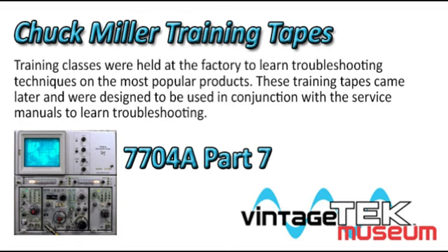R3039 grounds the cover, which covers this inverter circuit. C3039 couples any currents that might capacitively couple into the cover right back into the inverter circuit. Now off to the left of T3030, C3030 couples any currents that might be capacitively coupled into that secondary winding, couples them back into the inverter circuit. See, it's important that all of the currents be contained within the inverter circuit and not get into the chassis.